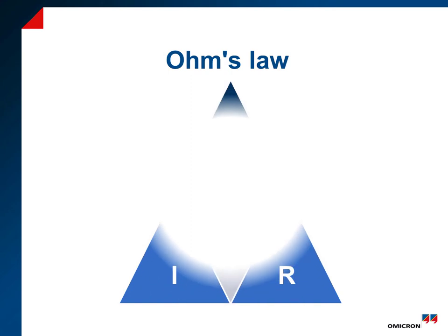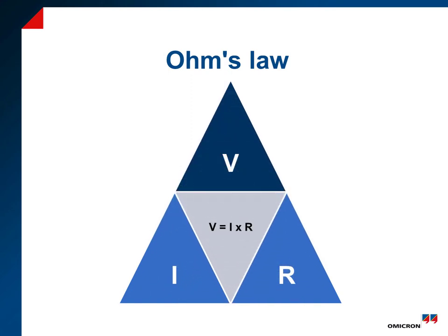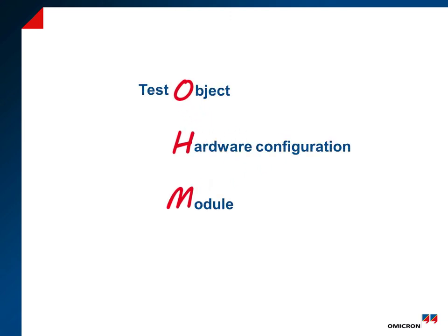Allow us to redefine the traditional electrical formula known as Ohm's Law. We shall tweak this formula to describe it as Ohm's Law according to Omicron. Ohm now represents Test Object, Hardware Configuration, and Test Module. The Test Object contains the information of the device under test. The inputs, outputs, and other specific signals are defined in the Hardware Configuration. Finally, operating the Test Module is when you perform the test. All this information must be completed before you conduct your test.